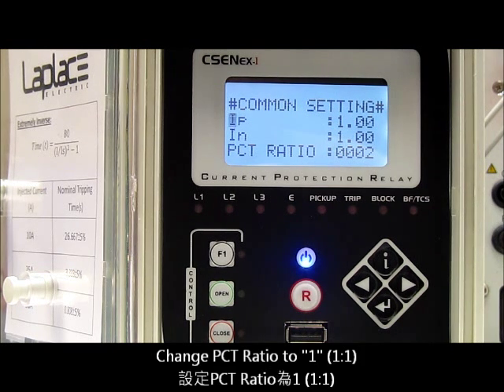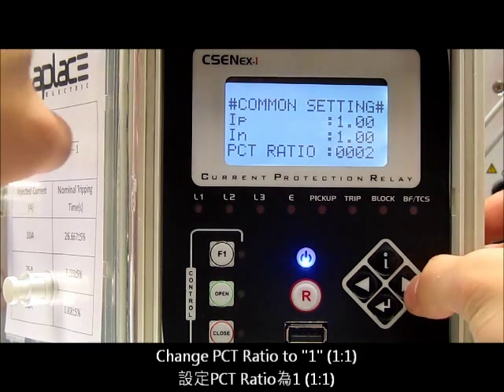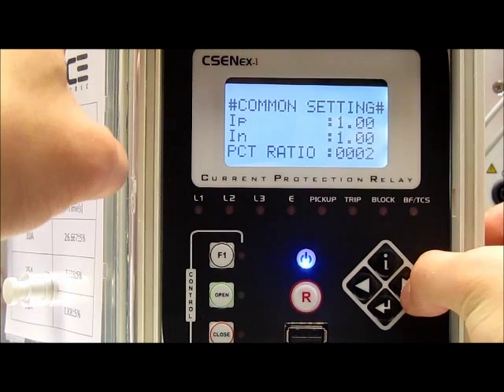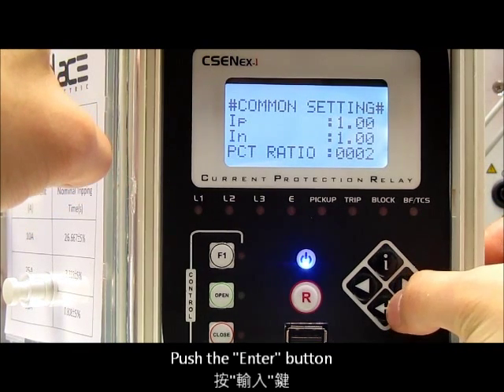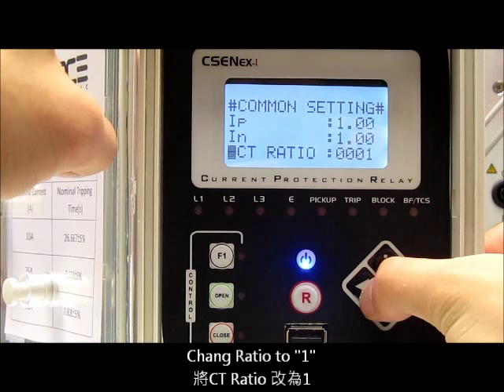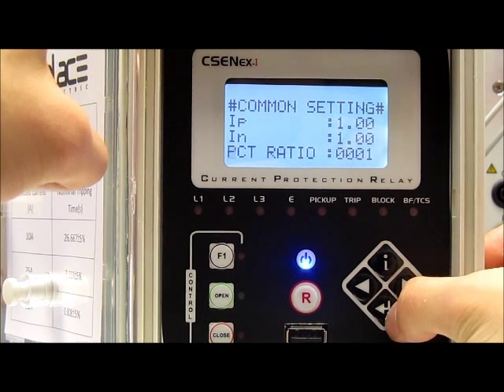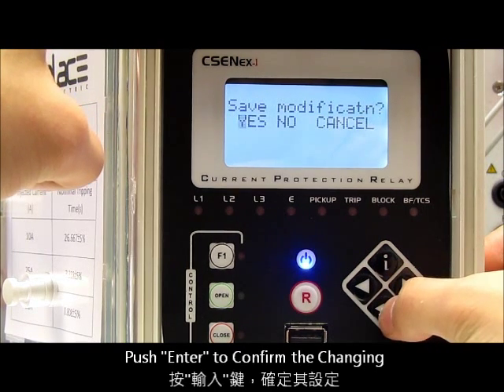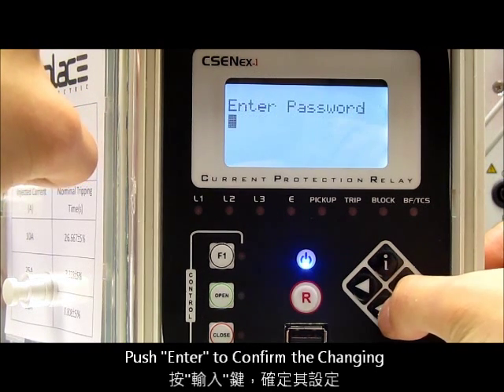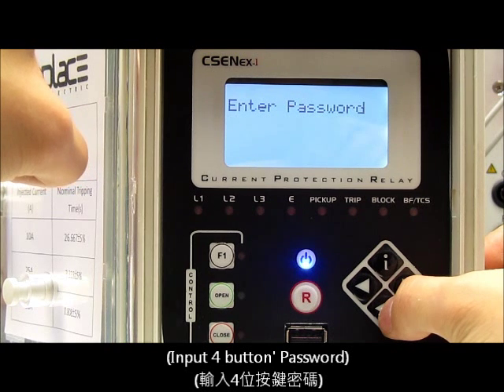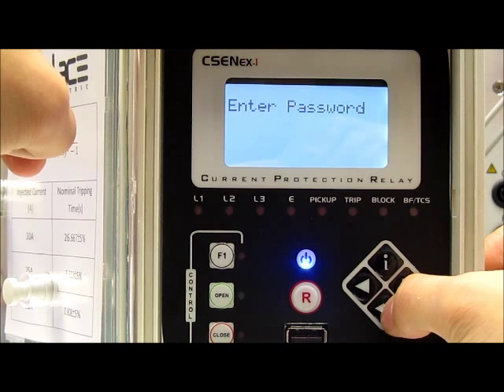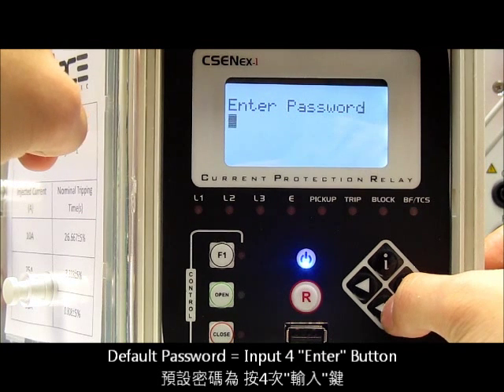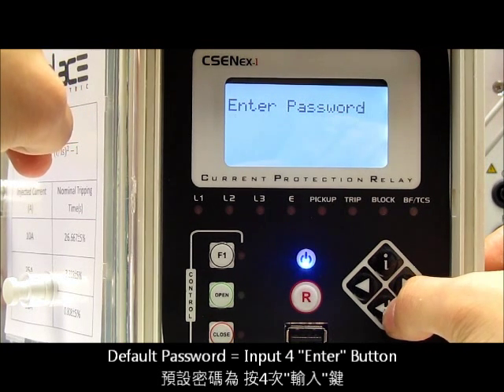Firstly, we change the CT ratio to 1. Push the enter button, change it to 1, and push enter. Due to the security protection, we need to enter the password — the default password is four enter button presses.